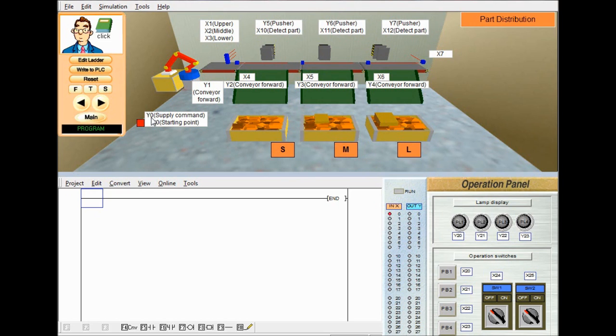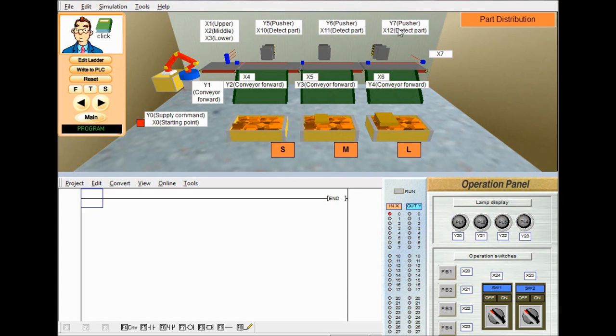If we give a command to Y0, then this robot arm picks up a part randomly and places it into this conveyor. The part will be moving along this direction. If it is a small part, we have to stop conveyor Y2 and activate Y5 pusher for dropping that object into this box. If it is a medium part, we have to stop conveyor Y3 and activate Y6 pusher. If it is a large size part, then we have to stop Y4 conveyor and activate Y7 pusher for dropping into this box. This is the control objective that we have to do.